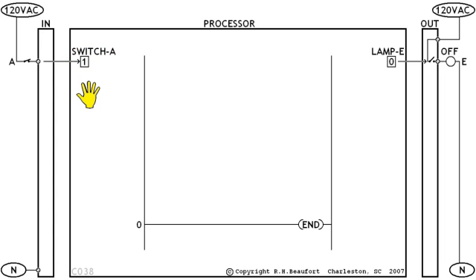But here's one very common misconception that confuses a lot of people. The transfer of information from the switch in the field to the bit box inside the processor does not take place instantly. Yes, it happens very rapidly, usually several hundred times a second, but it does take a certain amount of time. And understanding those timing issues is often the answer to certain beyond beginner types of problems. We'll dig deeper into this subject in our next lessons.